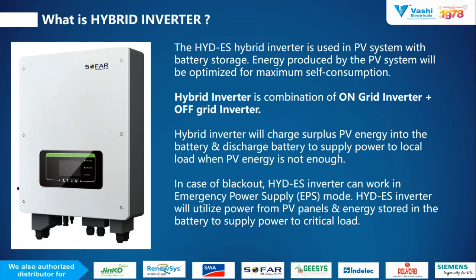Unavailability of grid power means grid supply is not available, or PV power is not available, meaning solar power is not available. At that time, it will use the storage battery power, the stored battery power. That is, the power stored in the battery will be used to run your critical load, or the load at the home which you are using.